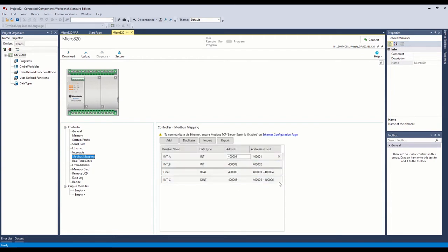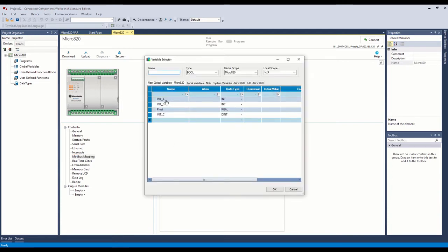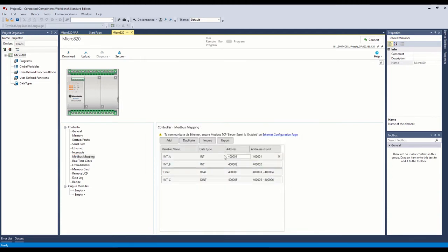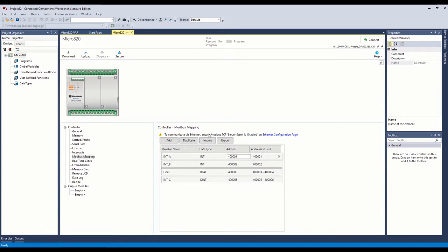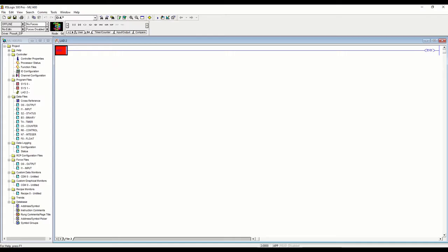Under the Modbus mapping, all we have to do is map some variable names. If you want to add one to the server you just click it and it'll automatically grab the next Modbus address you want to start at and map it for you. These are already being mapped to the Modbus server from the Micro820. So we're going to configure the 1400 to be the master and grab the information out of the 820 over Modbus.